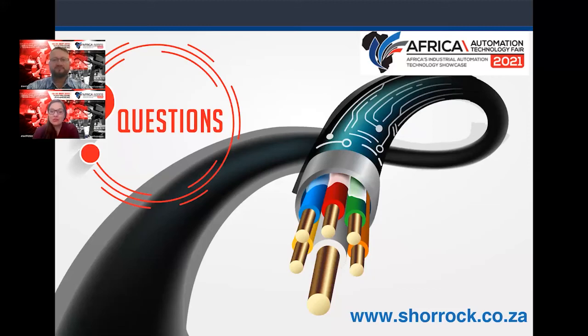Great. Does the Pro 2 PSU have ECB functionality? Yeah, so electronic circuit breakers can be divided into two areas. WAGO offers multi-channel electronic circuit breakers, which are separately available from the Pro 2 power supply. The Pro 2 power supply has full electronic circuit breaker functionality, but on the single 24-volt output. So there's no channel division on this. It will switch off the power supply if it reaches that electronic circuit breaker value, and it will trip at that value. We can also then set the delay time for that trip.